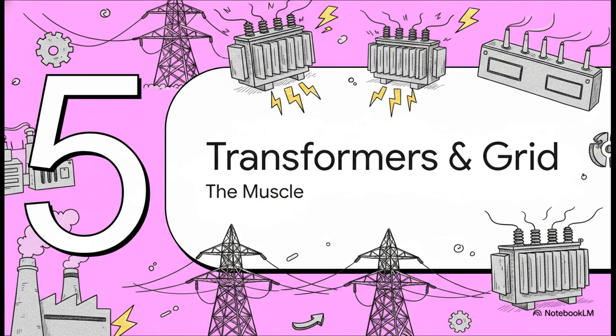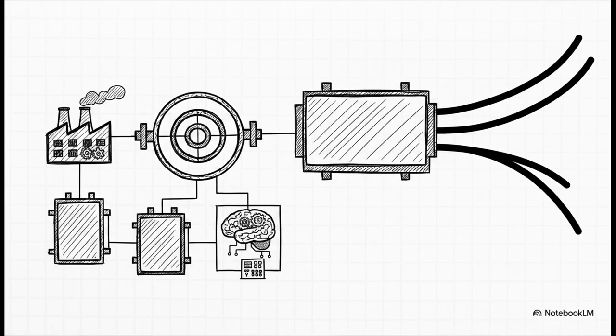Let's move to our final stop and see how this all builds together in Section 5, Transformers and the Grid, the true muscle of the whole operation. Now, while Powerformers are undeniably revolutionary, the vast majority of the world's power plants still use traditional generators, and that means they rely heavily on transformers, the muscle I just mentioned, to push all that generated power out into the world. In a standard setup, you generally have 4 main types of transformers. You have the unit auxiliary transformer and the startup transformer, both of which step power down just to run the plant's own internal equipment. Then you have the excitation transformer, which feeds that critical AVR system we talked about earlier. But the absolute heavy lifter is the main step-up transformer. In a lot of large plants, this colossal machine is wired directly to the generator, sometimes without even a single circuit breaker in between, forming one massive unified generator transformer set.